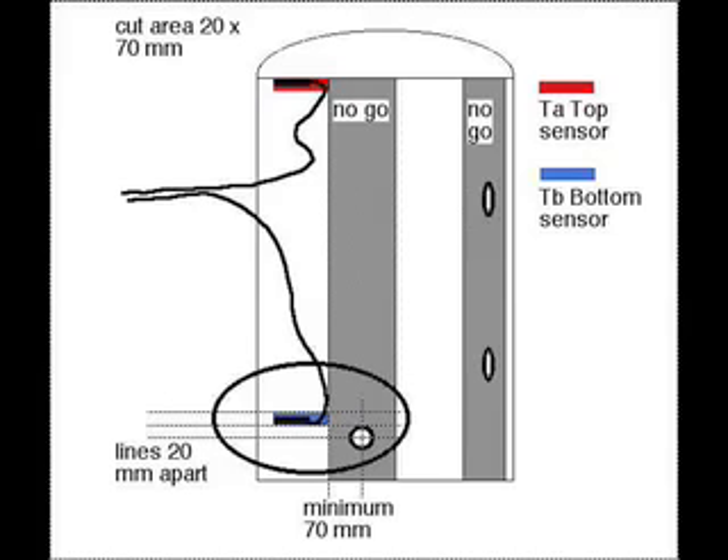Where do you fit the lower sensor? It should be 20 to 40 millimetres above the height of the midpoint of the coil pipe that leads to the panel, and at least 70 millimetres to the side of it. Again, cut a horizontal hole 20 by 70 millimetres, take the insulation out, insert the sensor, replace the insulation in the same orientation, and seal it completely with aluminium tape. Make sure the cables for the sensors cannot come loose — this must be a foolproof installation.